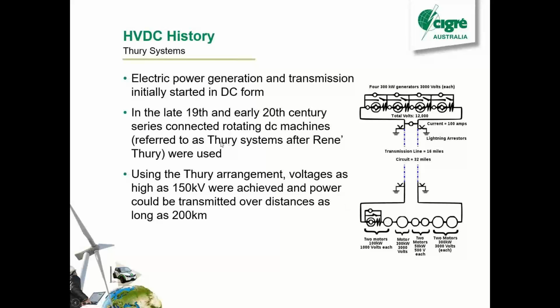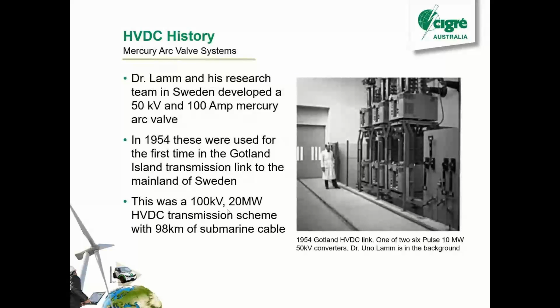So that was called a Thury system. Yeah, they could get voltages pretty high, actually, 150 kV, and they could get up to 200 km, which is actually pretty impressive considering. But obviously the losses weren't great, and there's all sorts of issues with the machines, with brush wear and all that sort of thing. So we moved on to something better.